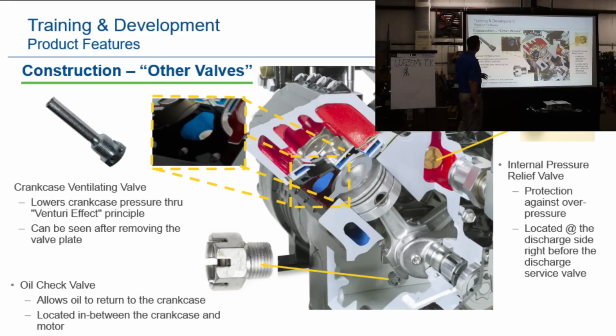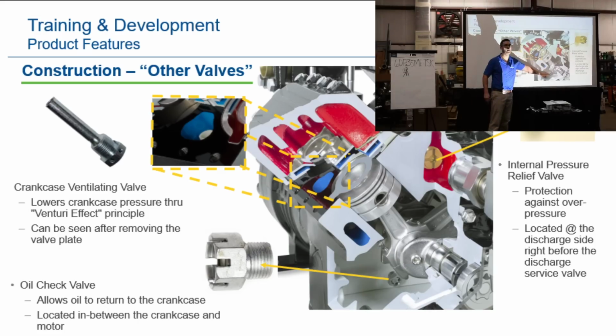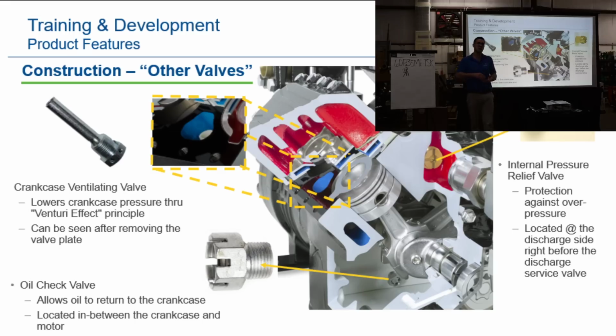Some of the things inside them. We got a crankcase ventilator valve here. We got an oil check valve right down at the bottom. You see right here, that's an oil check valve, free floating. And then we got an internal pressure relief. So if that differential pressure gets too high, it's going to relieve. It'll make a loud sound, really loud.